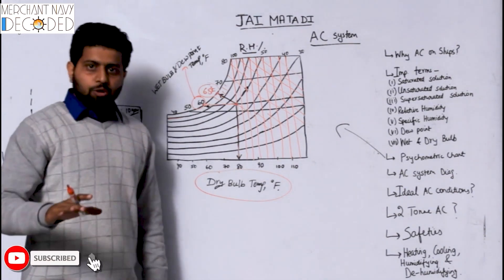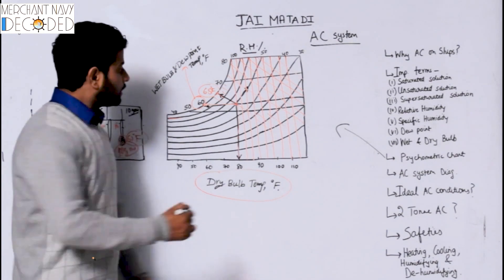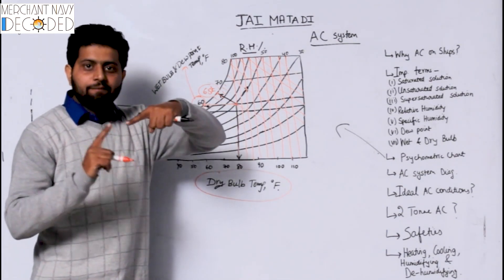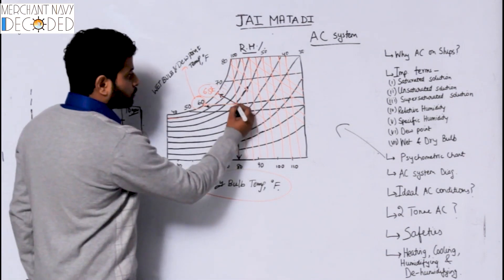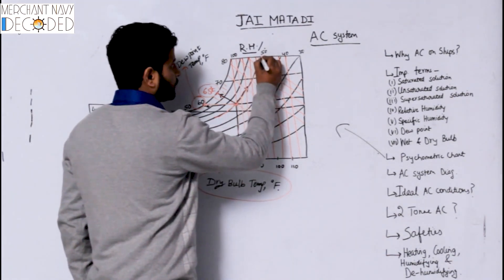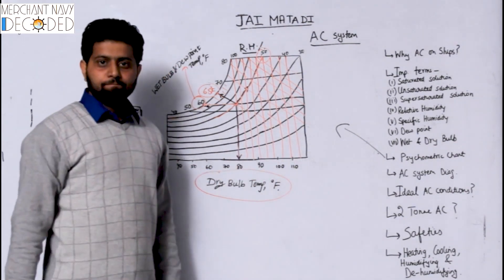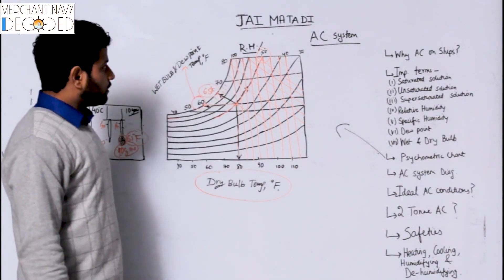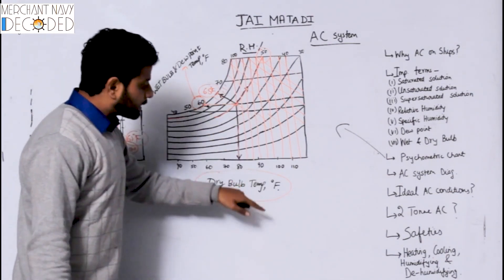There is a question: is the dew point a horizontal line, a vertical line, or what? It is a horizontal line. So by knowing your dry bulb and wet bulb temperature, you also know your dew point. And when you know this point, you follow the line and see it goes to a relative humidity of 50%. So you know the relative humidity and the dew point just from the wet bulb and dry bulb temperatures.